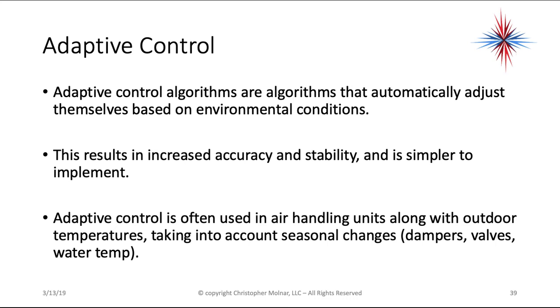Adaptive control is the final control algorithm. Adaptive control algorithms automatically adjust themselves based on environmental conditions, resulting in increased accuracy and stability and simpler implementation. Adaptive control is often used in air handling units accounting for outdoor temperatures and seasonal changes — adjusting dampers, valves, water temperatures, and first/second stage cooling based on outdoor conditions, which affects the building's ability to lose and gain heat through its walls, windows, and doors.